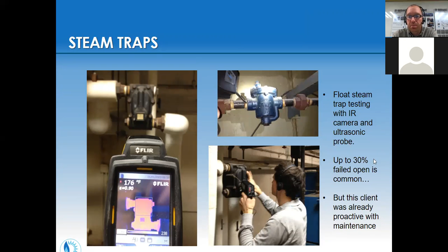Steam traps - as mentioned in the boiler program, there are steam trap assessments and surveys that can help identify failed steam traps. It's pretty common for up to 30% to fail in the open position.